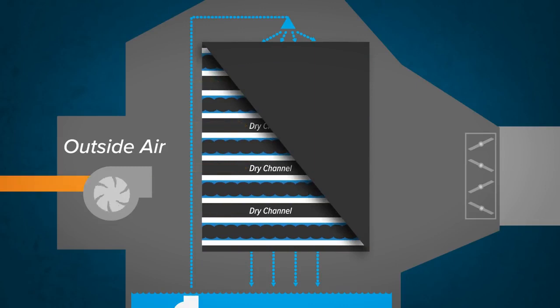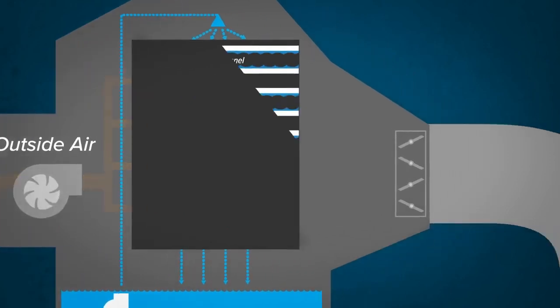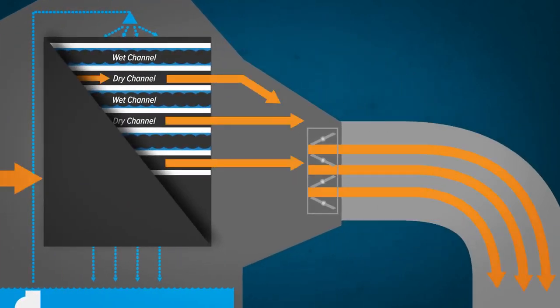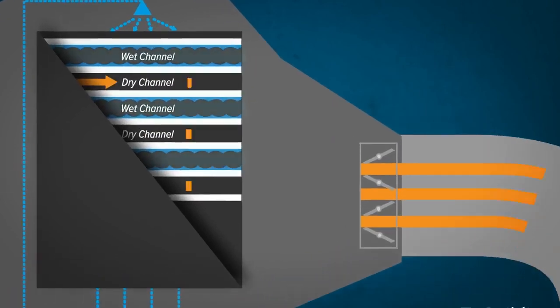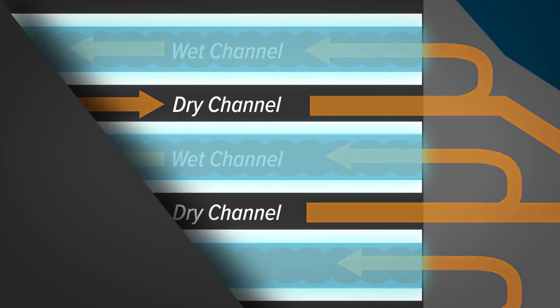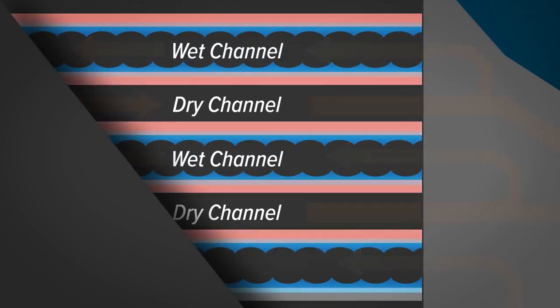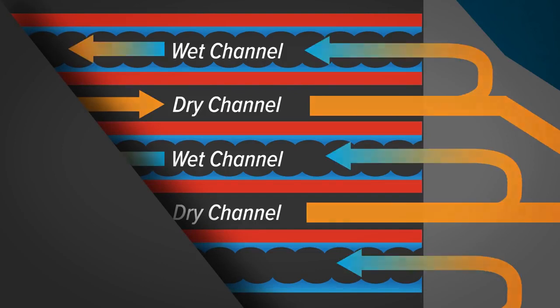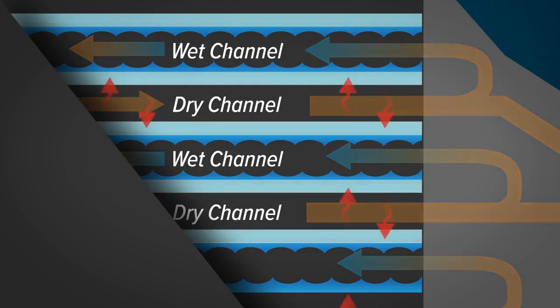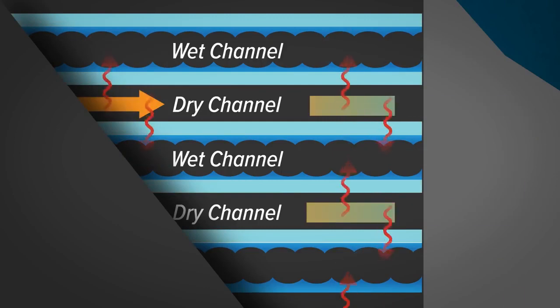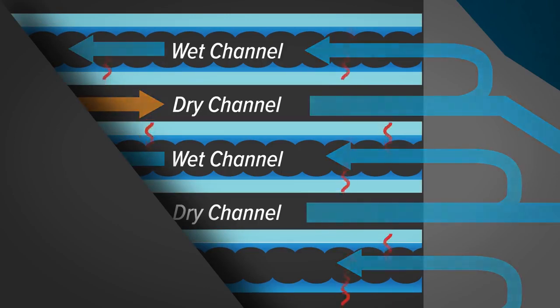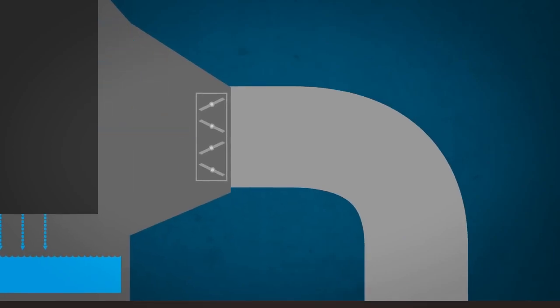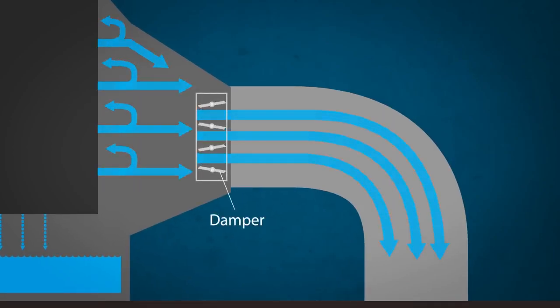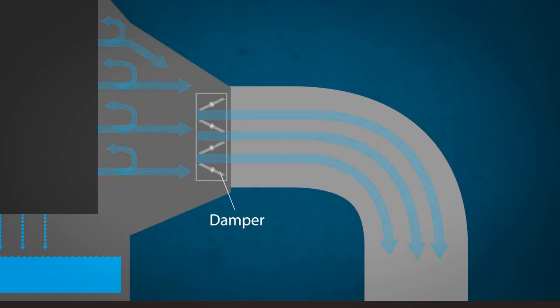Hot outdoor air enters the dry channels of the heat exchanger through a high-efficiency fan. After air passes through the dry channels, a portion of the air is supplied to the building, and the rest returns through the wet channels. This is where the evaporative cooling process takes place. The evaporative process cools the wet channel walls. As these walls cool, they absorb heat from the dry channel air, cooling the air delivered to the building. The portion of air supplied to the building is controlled by a damper that is set for the specific application.